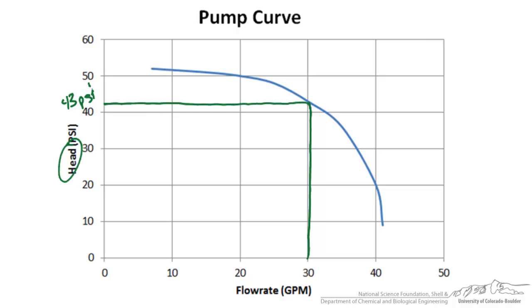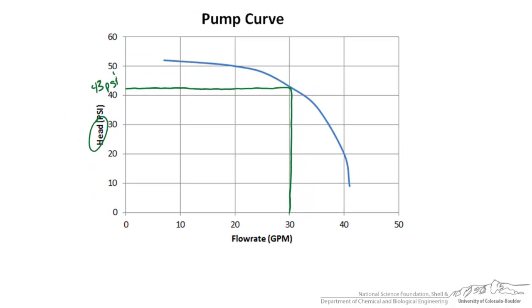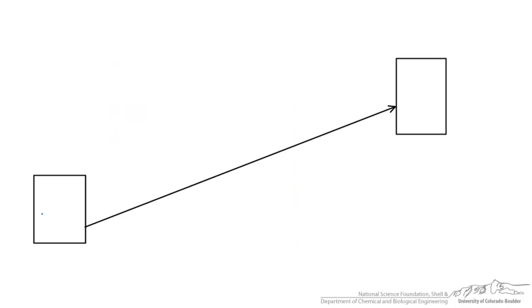Typically, on a pump curve, the head is in feet or meters. Here we designated it in psi so we can directly read off this chart. Let's draw a picture for our process so we can map this out and determine the maximum length of piping. We have a storage tank at a lower elevation than our heater, with a pump right at the outlet of the tank.